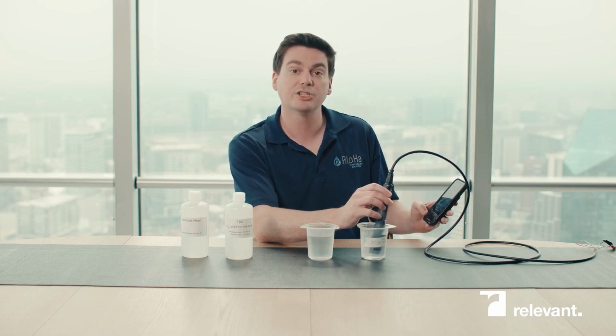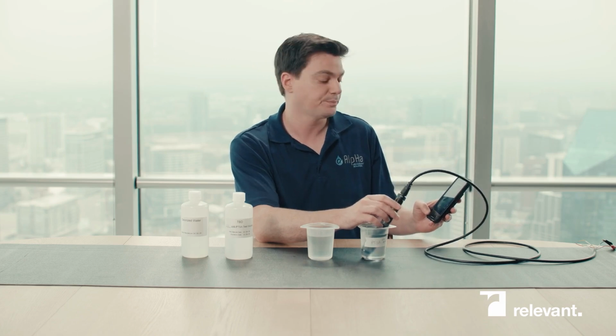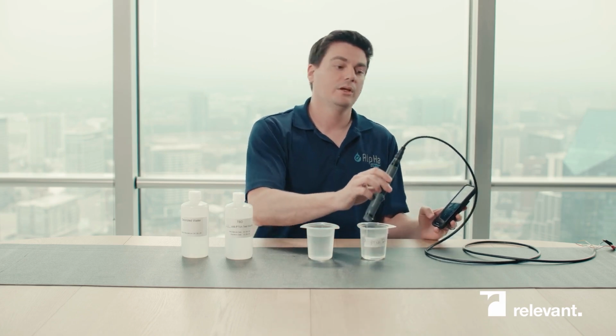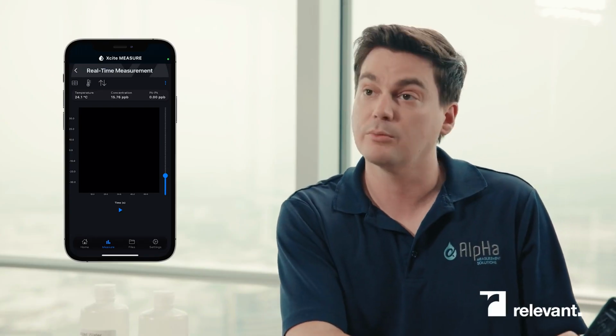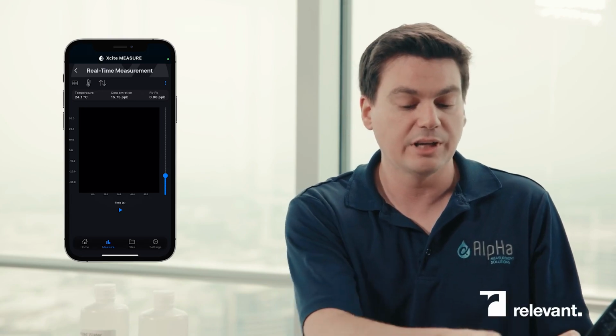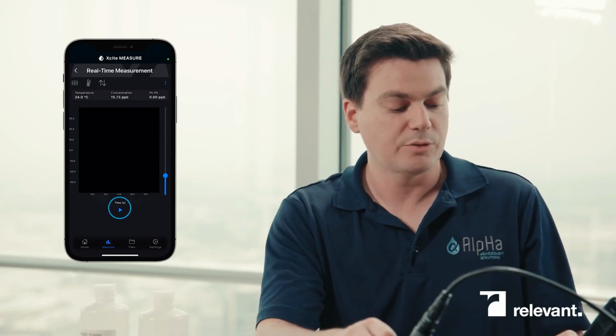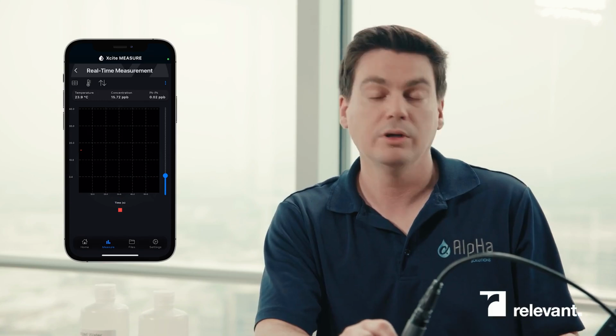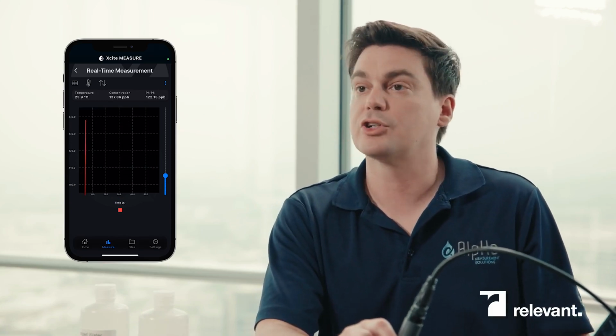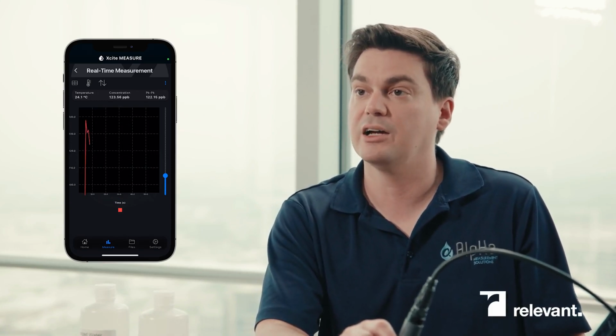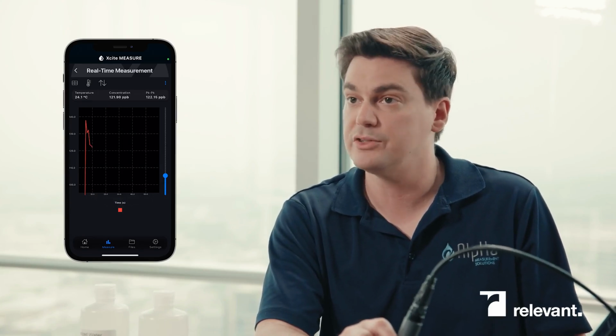And from here, that's it. You are done with your full calibration of your sensor, and you can get back into the measurement range as you can see. With the measurement range, you can measure in real time. But you need to let it know that you want to measure in real time. You do that with the play button right down over here at the bottom of the screen, and you can hit play. Once you hit play, the red line on the graph will start to track in real time the concentration of the sample you're putting the probe into.